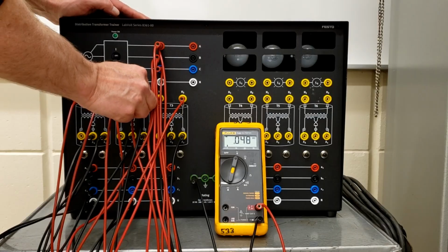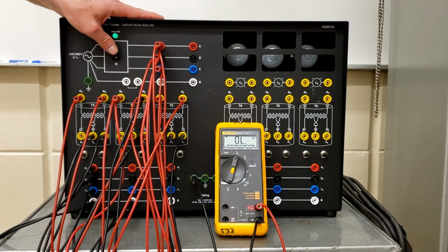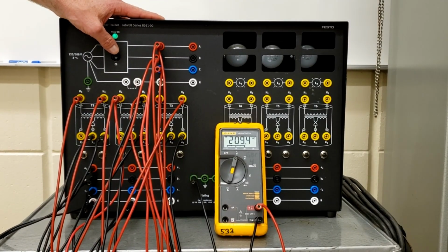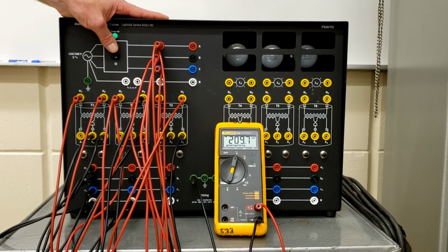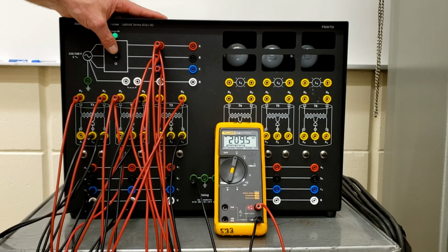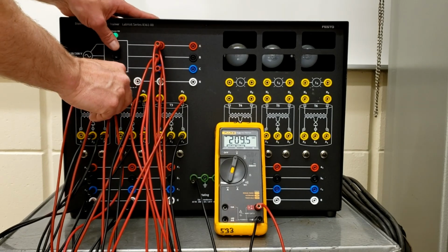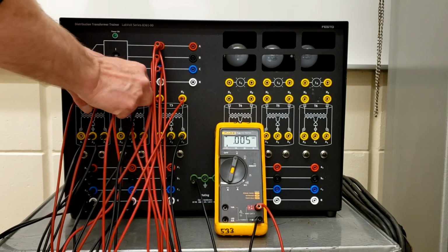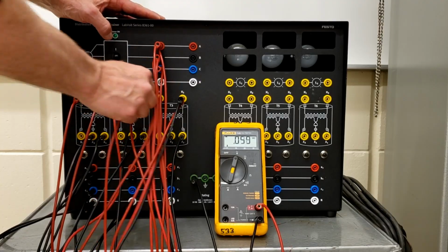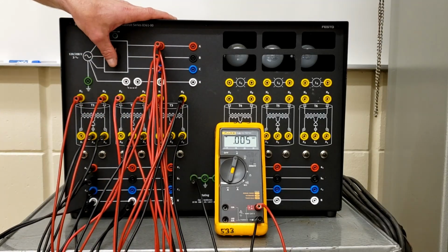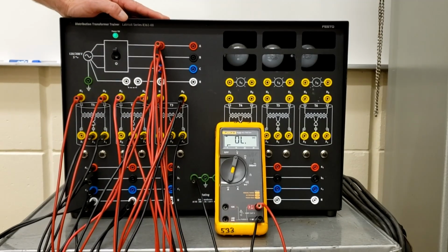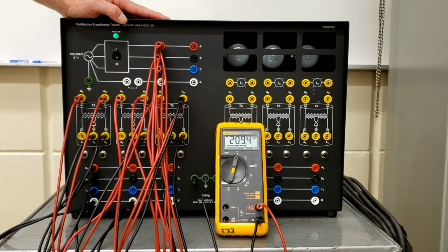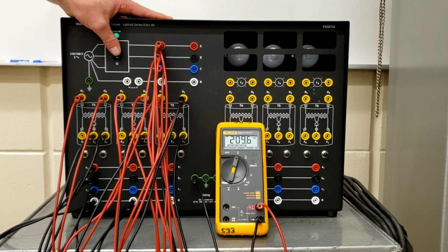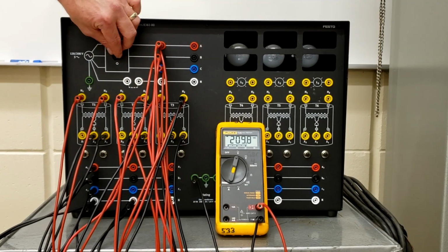Looking at the second transformer, it should be identical voltage. We're at 209. As I've mentioned numerous times, you'll find the voltage goes from around 207 to 210 on this floor. There's a big compressor on the other side of the floor, and when it turns on, the voltage sags for the entire floor, so some days we'll have higher voltages than others. Today we're having 209 volts on the primary, matching phase voltage on the delta with line voltage on the delta.